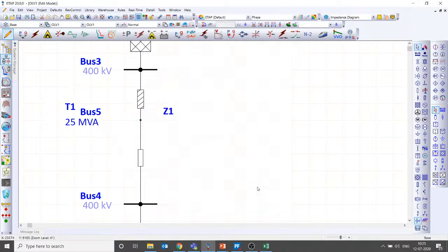Fine. So before going further, let me take a few questions from the chat box. Okay, Vishal Kumar asks what is the importance of the minimum short circuit current? Today we are talking about load flow, but I will still quickly answer. The minimum short circuit current is mandatory for motor starting studies, it is needed for transient stability, and also for harmonic analysis. It is also needed for protection, to validate whether your relays are able to pick up for the minimum fault current. So those are all the reasons why we need minimum short circuit current.